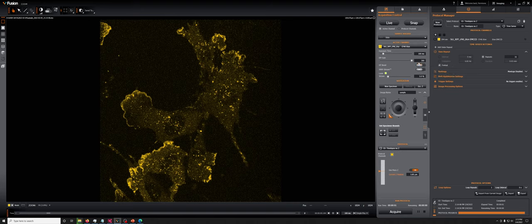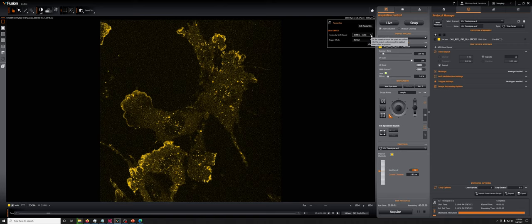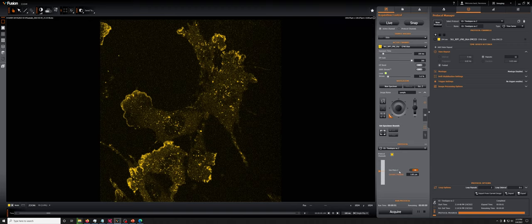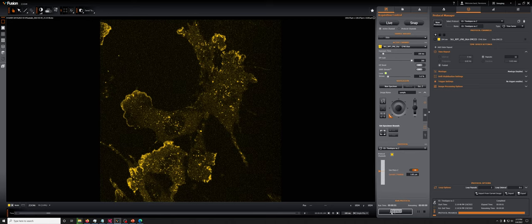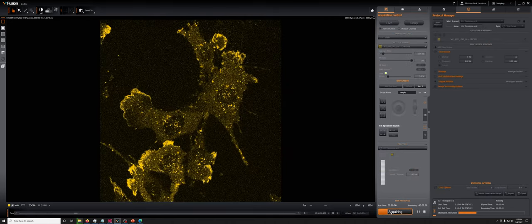This whole discussion is going to be about how to reduce that time as much as we possibly can. So right off the bat, there's something that we should make sure of, which is to have the camera in the 30 megahertz horizontal shift speed, which is what it's at right now. So if you had instead opted for 10 megahertz, which might lead to higher signal-to-noise, and we had done the same experiment under those circumstances, let's see what happens with that extra 44 milliseconds, whether it gets higher or lower.